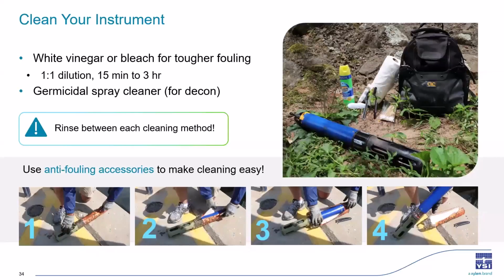And you don't want to be soaking all your sensor tips in bleach because some of them can have bad reactions. So if you're cleaning your instrument on the outside with bleach, just wipe it down or wash it down on the outside. You can also use germicidal spray cleaner for decon, like Quat, if your SOP calls for it. But be careful with that. Again, you want to avoid the sensor tips. Make sure you rinse your equipment off really well with water as well, especially between each cleaning method, so you're not mixing chemicals.